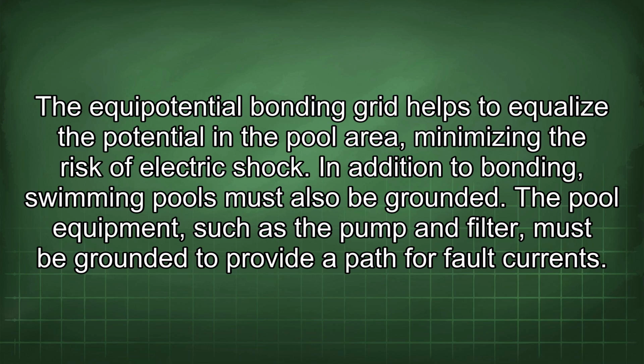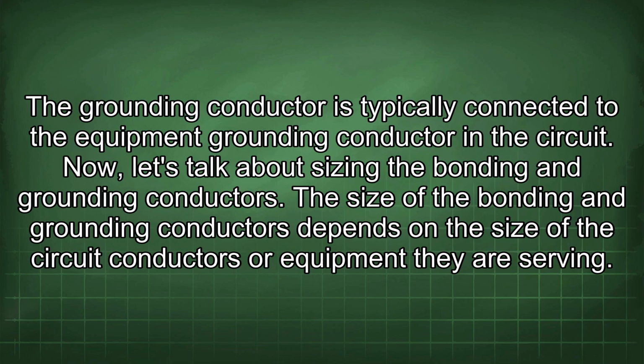In addition to bonding, swimming pools must also be grounded. The pool equipment, such as the pump and filter, must be grounded to provide a path for fault currents. The grounding conductor is typically connected to the equipment grounding conductor in the circuit.